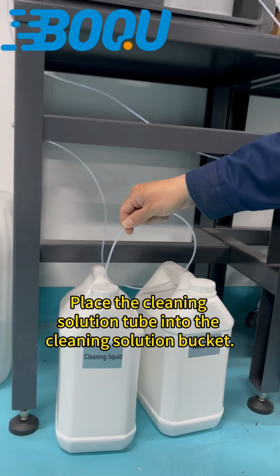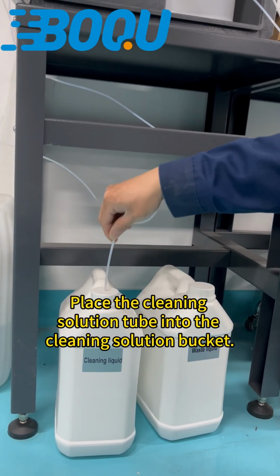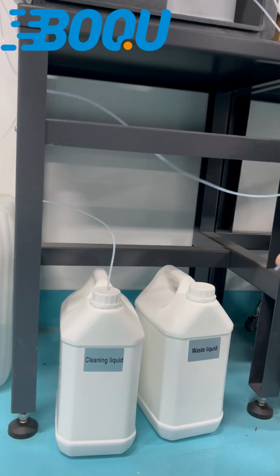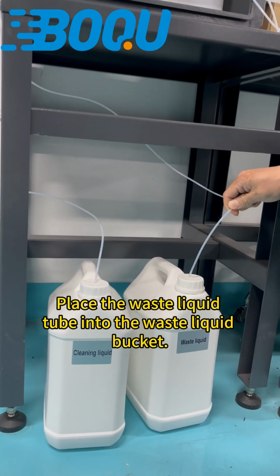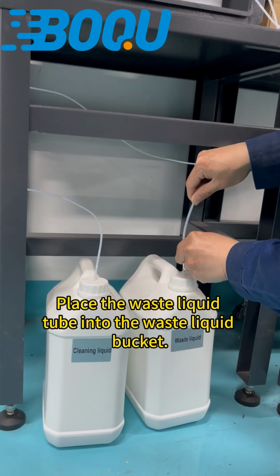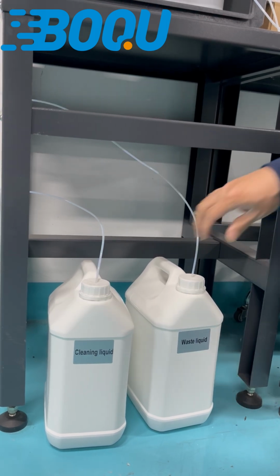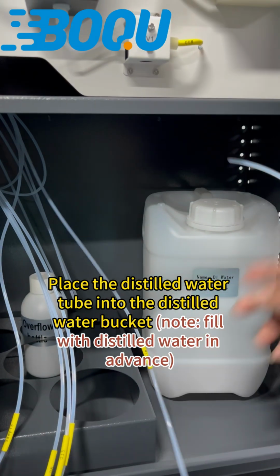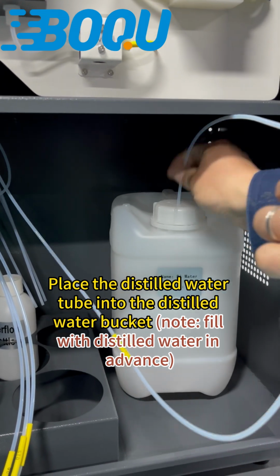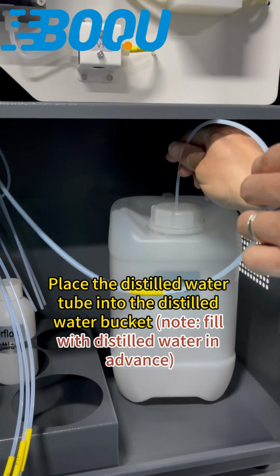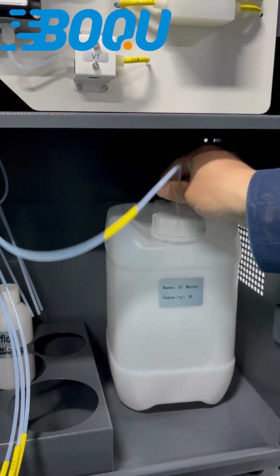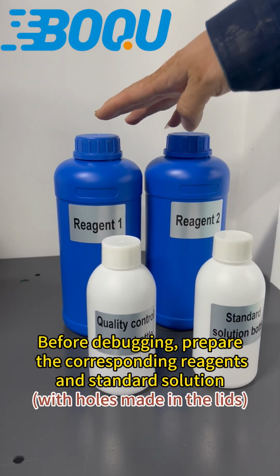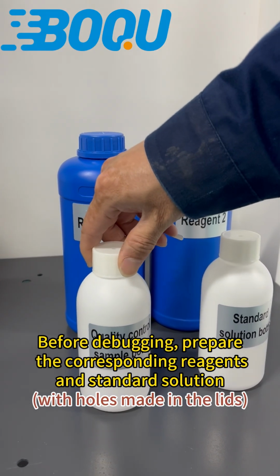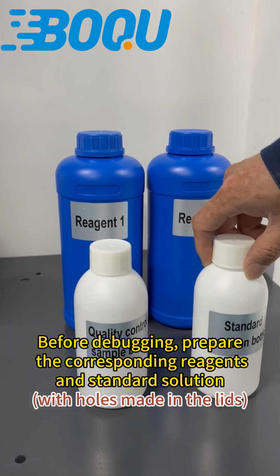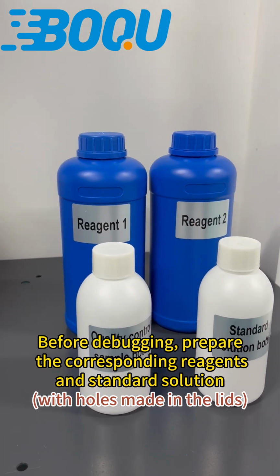Place the cleaning solution tube into the cleaning solution bucket. Place the waste liquid tube into the waste liquid bucket. Place the distilled water tube into the distilled water bucket. Note, fill with distilled water in advance. Before debugging, prepare the corresponding reagents and standard solution with holes made in the lids.